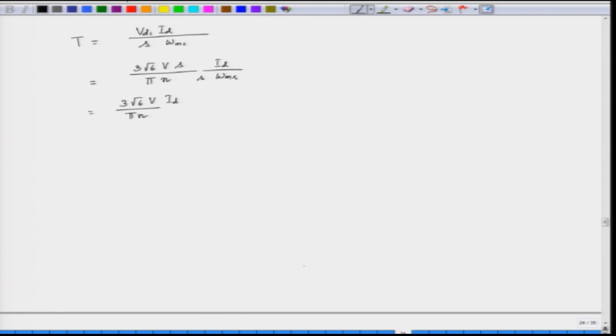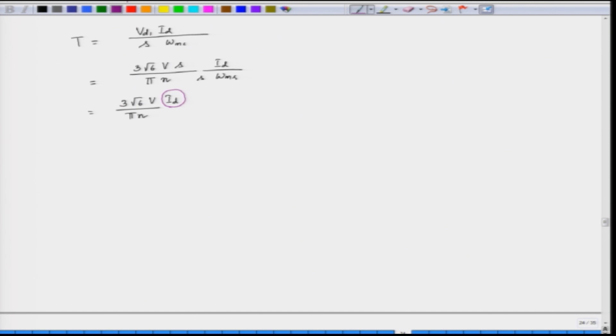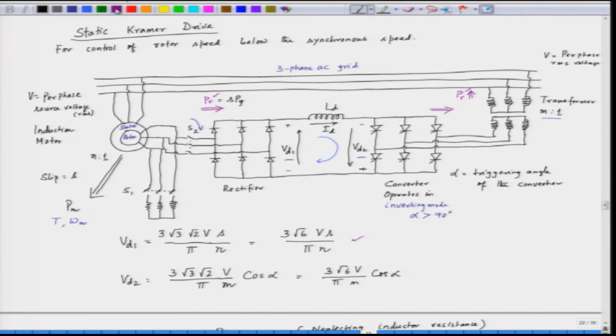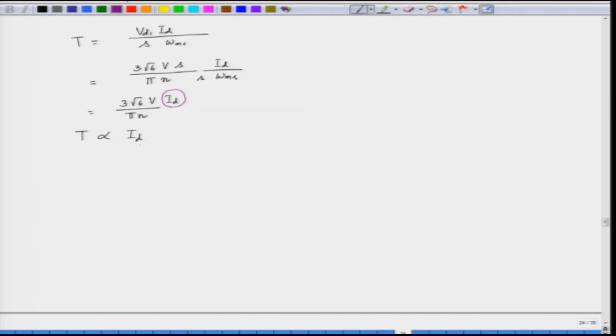If we see this torque equation, the torque is proportional to I_d, since V is constant and 3√6, π, and n are all constant quantities. So T is proportional to I_d. If we want to control the torque of the induction motor and hence the speed, we have to control the DC link current I_d.